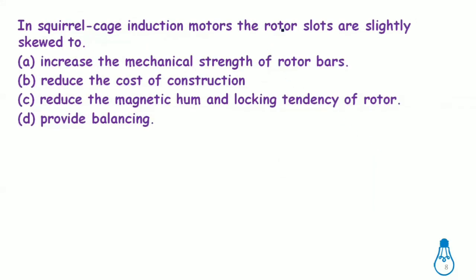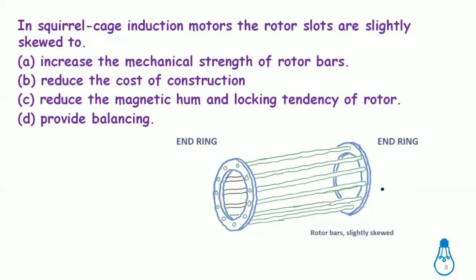In a squirrel cage induction motor, the rotor slots are slightly skewed — meaning the rotor bars are not parallel to the shaft but placed at some angle. The main reason for skewing is to reduce magnetic hum and locking tendency. Locking tendency means the rotor tends to lock at a particular speed, and skewing the rotor bars helps avoid this tendency.